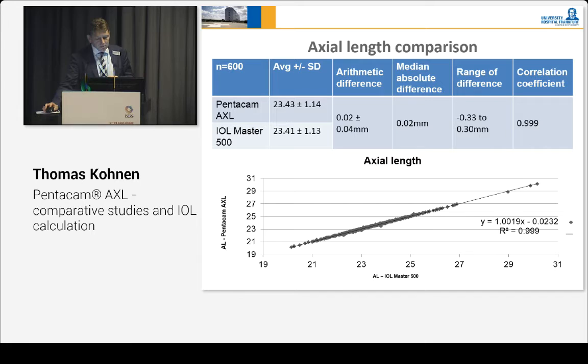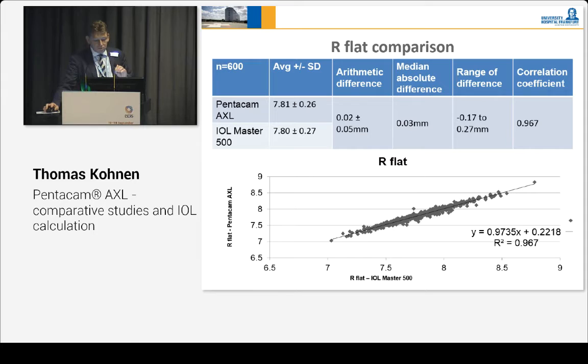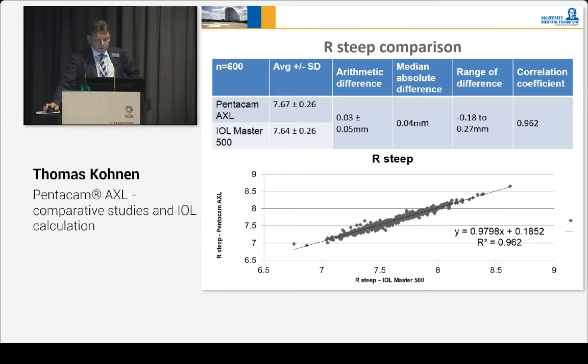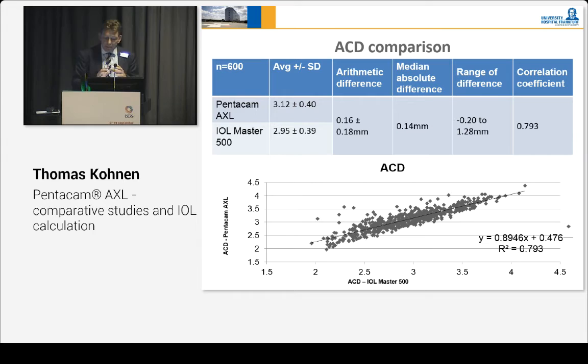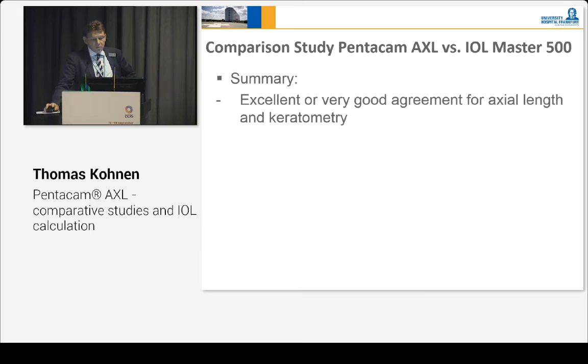As you can see here, the average with standard deviation, arithmetic differences, mean absolute differences, range of differences, and the correlation coefficient showed a very good correlation — almost 100%, as you can see in this graph. Axial length comparison and the corneal flat and steep curvature measurements also show excellent correlation. The ACD comparison shows slightly different results, but still a correlation coefficient of 0.79, so almost 0.8.